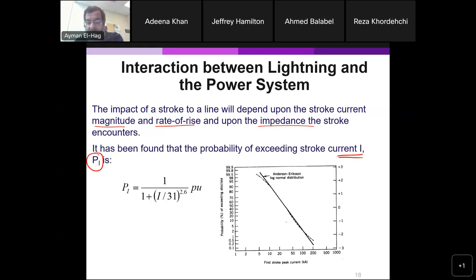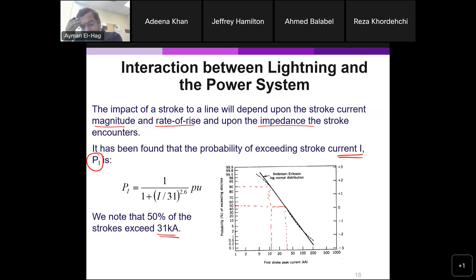Okay, so you have the drawing for this here. For example, this is the probability. So with 50% probability, the current value will exceed 31 kiloamps. With 90% chance, the current will exceed maybe 12 kiloamps, and so on and so forth. So this curve can give you the probability of that. What is the probability that a certain surge will exceed certain current values?